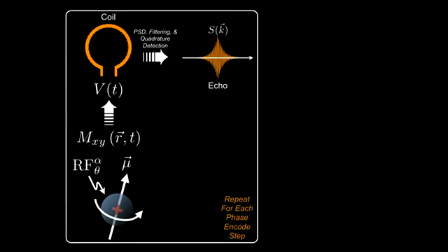When we have those, so let me back up. We have to do this to acquire a sufficient number of echoes. An echo is a series of K points, right? But we need all of the K points to represent the entire image. And so typically we have to repeat acquiring the echo for all the different phase encoding steps. So if our image, we'll look at some examples, is 128 pixels wide and 96 pixels top to bottom, that 96 is usually going to be the phase encoding direction because it's lower in number. We're going to have to repeat this process, say, 96 times. And that's one reason that MR can be relatively slow.